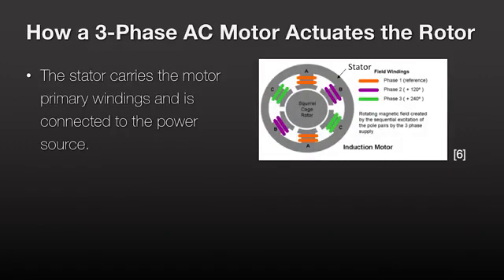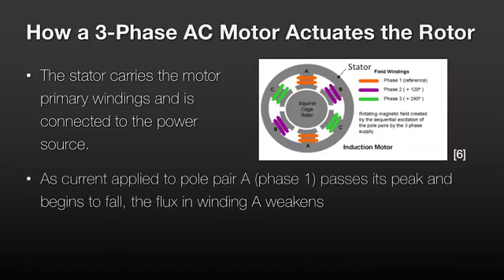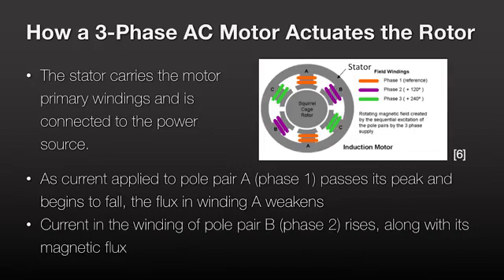The three field windings are out of phase by 120 degrees with each other. As current applied to pole pair A, in other words phase 1, passes its peak and begins to fall, the magnetic flux induced in winding A weakens. Current in the winding of pole pair B, in other words phase 2, rises along with its induced magnetic flux.